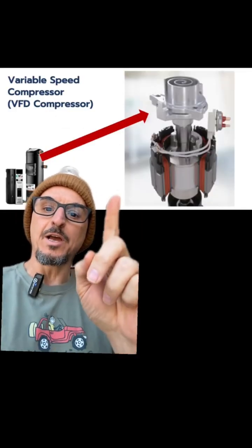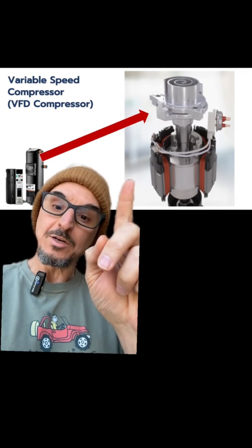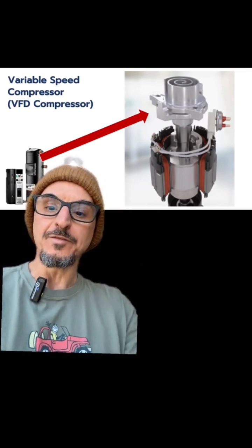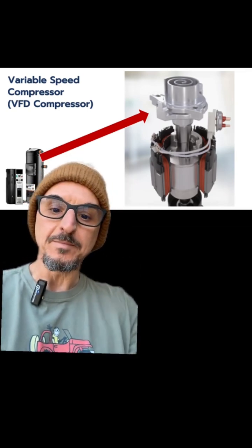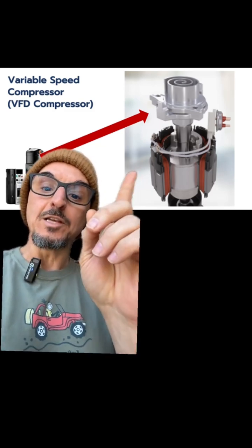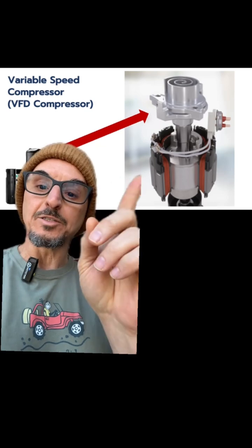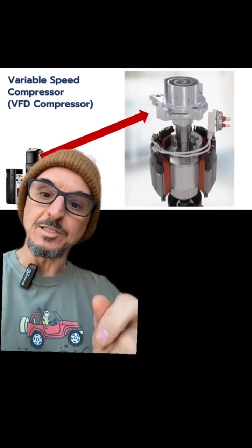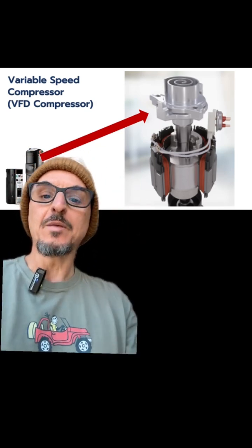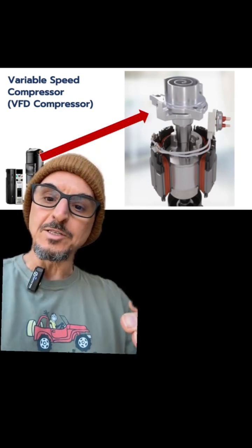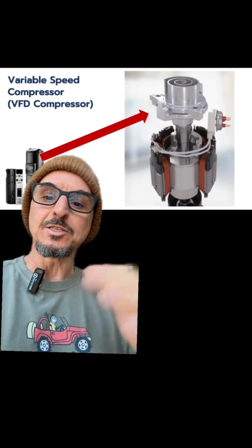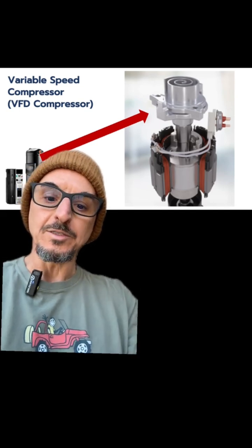Next we're going to look at the variable speed compressor, otherwise known as the inverter compressor or the VFD compressor. The main difference here is you're actually changing the speed of the compressor to match the capacity required. So if you needed 50% capacity, you would slow the compressor down to 50%. That's the main difference between this compressor and the digital compressor.